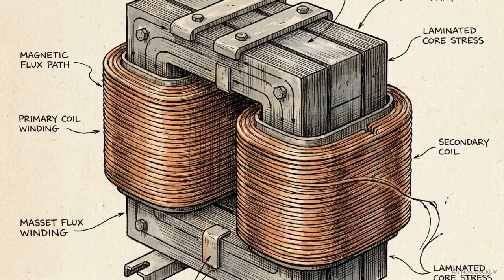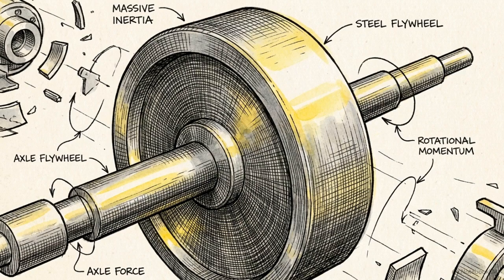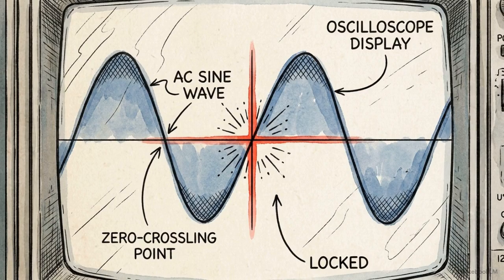When a short circuit happens exactly at the moment the voltage wave is at its highest peak, the result is what engineers call a symmetrical fault. The amount of current surges to massive levels, but the wave itself remains vertically centered and predictable. But the electrical grid is packed with transformers and motors that create inductance. This physical property, measured as the system's X/R ratio, acts like a massive magnetic flywheel, violently resisting instantaneous changes to current flow. The absolute worst timing for a fault is the exact millisecond the voltage drops to zero. Engineers call this a 0-degree closing angle.